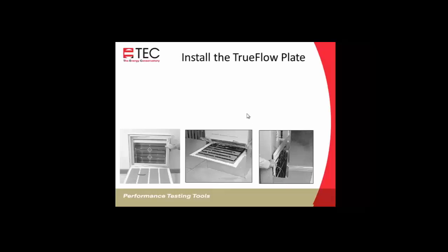Next, we'll install the TrueFlow plate, and as you can see, you can install that at a remote filter grill. If you've got a filter grill right at the air handler, either horizontal or vertical, you can install it there. And if you have one like is pictured at the right here, where you have a return drop, you want to make sure that the spacers are on the top, because as air is coming down that drop, there's going to be a lot of airflow at the bottom, and if you have that spacer at the bottom, you'll miss some of that. You'll be adding resistance to that airflow where it really doesn't need to be.